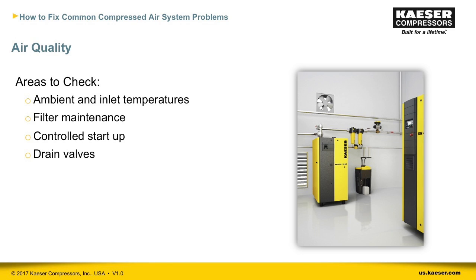If you shut your air system down at night or weekly, when you restart the system, the air velocity will be very high until the system gets up to pressure. This can overrun your air treatment equipment temporarily. If you have sensitive equipment, you should consider what we call an air main charging valve to control airflow during startup.